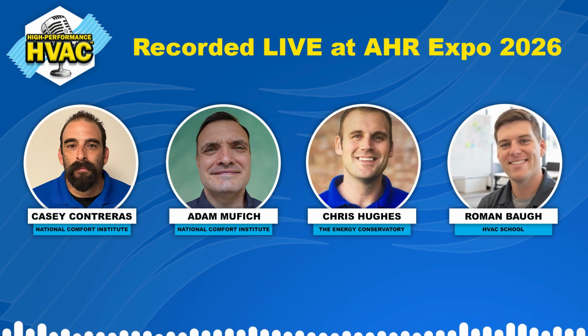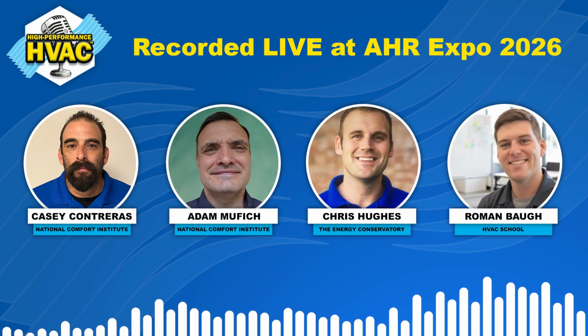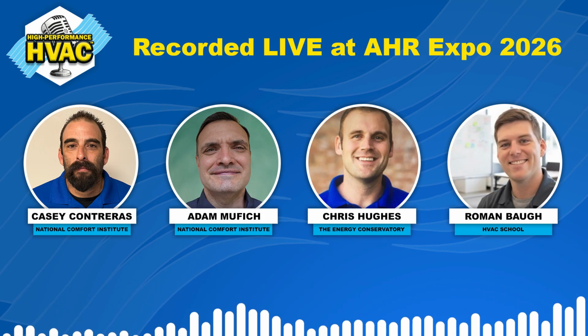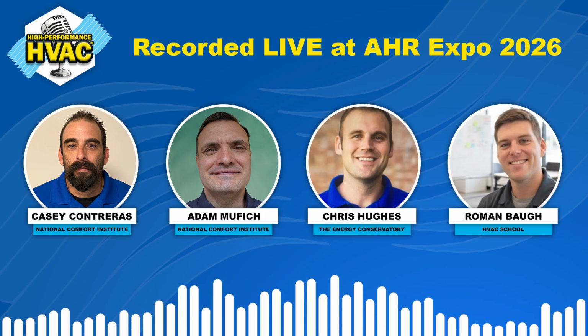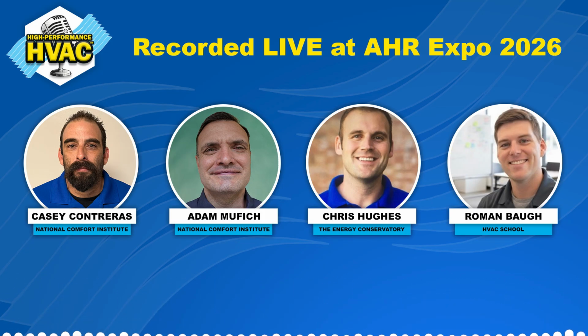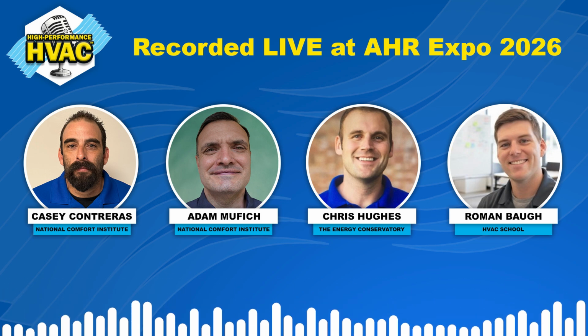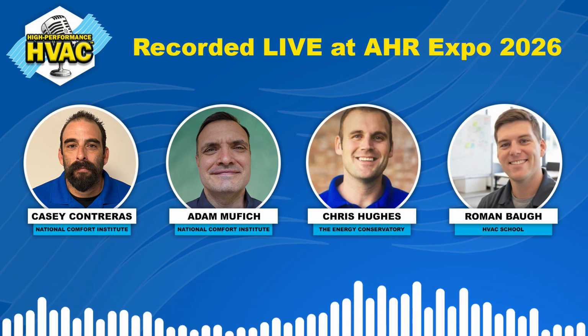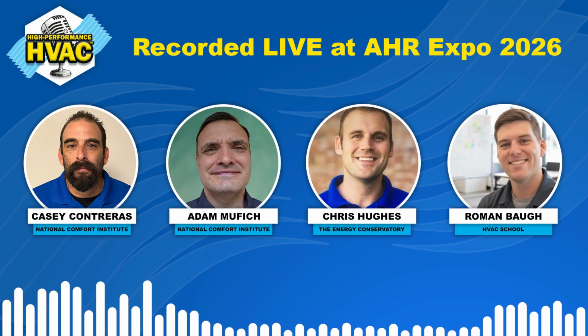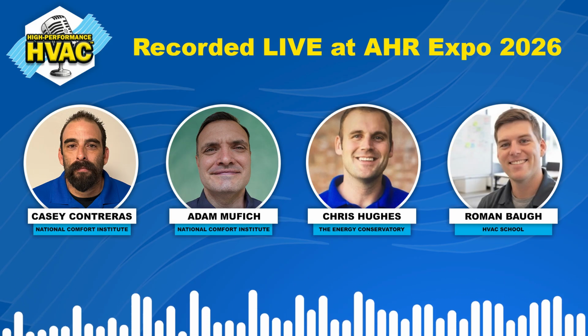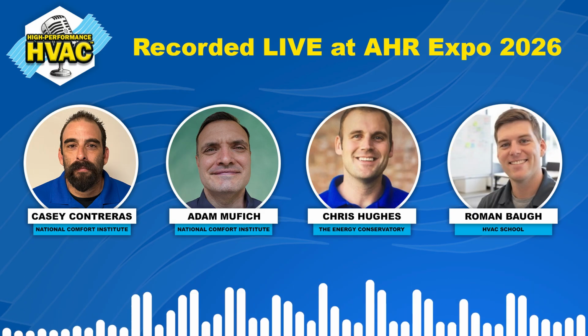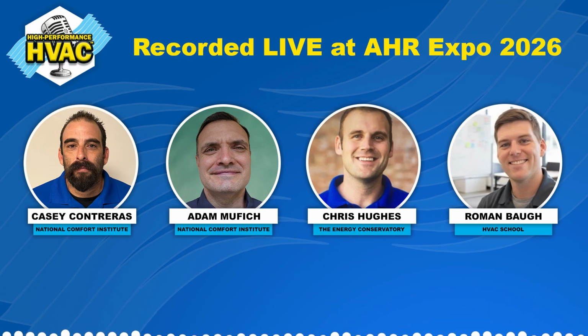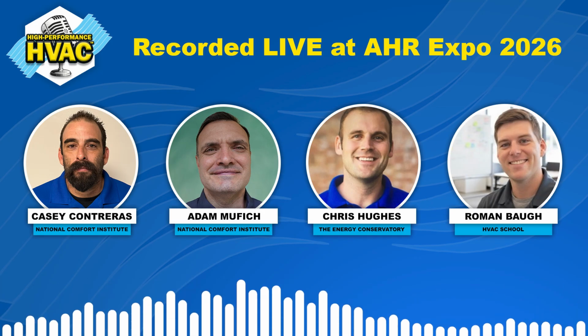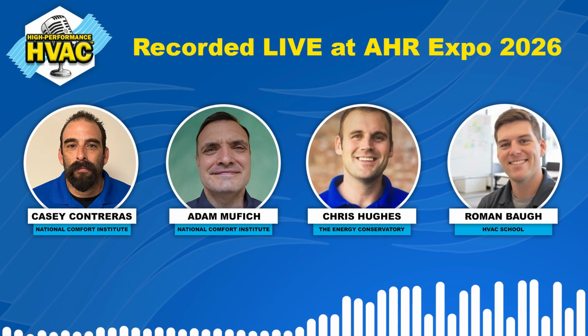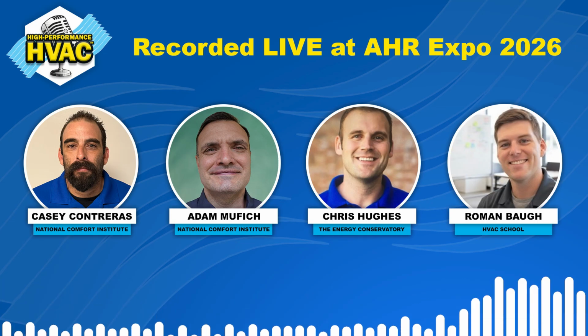But so I reached out to some local guys. I'm like, what do y'all do? And surprisingly, a lot of them are like, well, we don't really deal with that much. We don't push and pull refrigerant that much in the winter. Because heat pumps really aren't big up there yet, in my opinion. It's just gas furnace problems that they're dealing with, and there's not a lot of heat pumps. And then one guy told me, honestly, we'll just postpone that part of the job till it gets warm. Because a lot of times we can't even get the outdoor unit off the ground because it's frozen to the ground. Yeah, that's a big one too, right? We need to go out there with a heat gun and just heat it up. Yeah. But I have seen people do that before too.